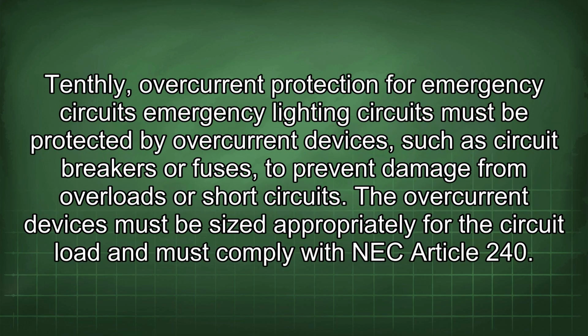Tenthly, overcurrent protection for emergency circuits. Emergency lighting circuits must be protected by overcurrent devices, such as circuit breakers or fuses, to prevent damage from overloads or short circuits. The overcurrent devices must be sized appropriately for the circuit load and must comply with NEC Article 240.